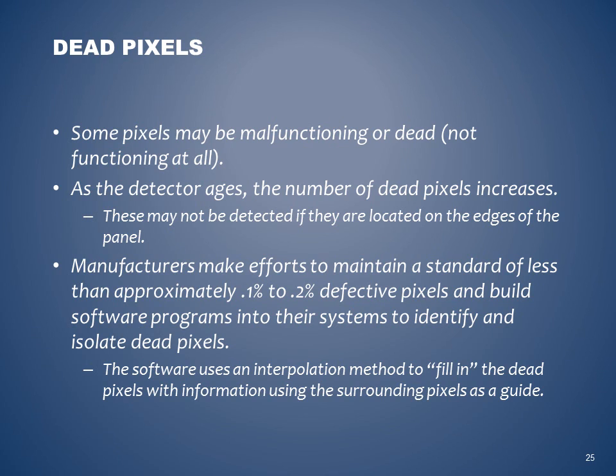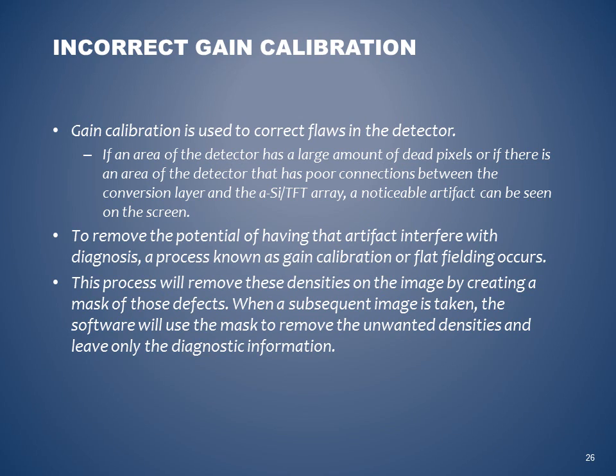Manufacturers make efforts to maintain a standard of less than approximately 0.1 to 0.2% defective pixels and build software programs into their systems to identify and isolate dead pixels. So know that they want less than 0.1 to 0.2% defective or dead pixels. The software uses an interpolation method to fill in the dead pixels with information, using the surrounding pixels as a guide. Incorrect gain calibration. Gain calibration is used to correct flaws in the detector.